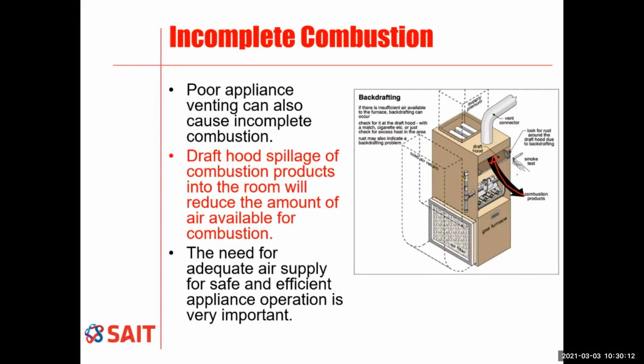So you could always do a match test. I can't believe they have a cigarette there. You can do a match test to see if you have proper draft, meaning that the smoke should be going up into the draft hood and out the vent.